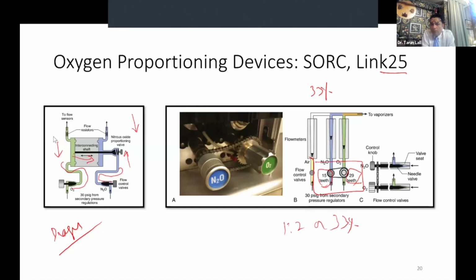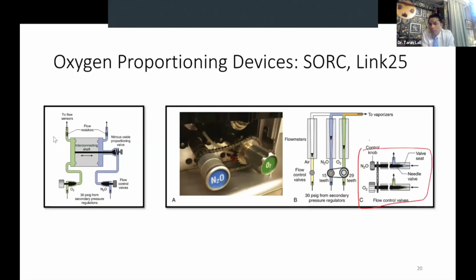The further reduction in oxygen occurs at the level of the flow control valve. As you can see in this diagram, the shape of the spindle in the two flow control valves is slightly different. Oxygen is the sharper one, and this steep taper results in more nitrous oxide flowing at the same level of valve opening. What we had here was 1:2. By the time it leaves the flow control valve, it becomes 1:3, because more nitrous oxide can pass through the flow control valve. Therefore the output is at least 25% oxygen, which is why it is called a Link-25 system.